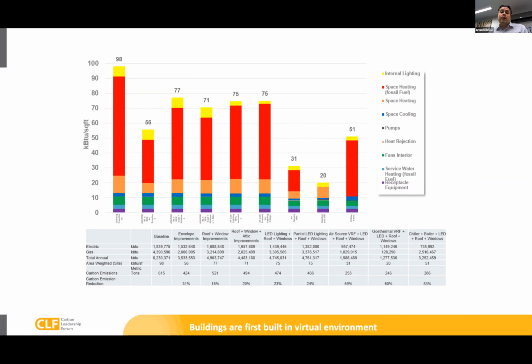By upgrading the HVAC system to primarily a VRF system, DOAS, air source VRF, we found that we could get the building down to an EUI of 31. We evaluated both geothermal and traditional systems as well, and obviously the geothermal system performed the best at 20.